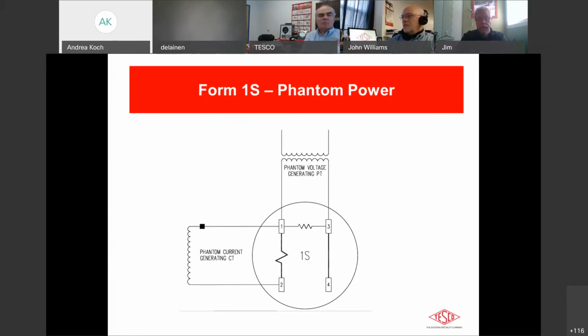so that's a big use for a 1S installation these days. Right, and actually, I did a TESCO Tuesday presentation a few weeks back on smart metering, which is these smaller format meters that are going onto LED streetlight poles and measuring some other interesting applications where you need a small format meter. Their meter form is basically a 1S, right? They've got a single coil for the voltage and a single coil for the current. There's some other electronics in those devices used to control the output, so they're dimming lights and turning them on and off and things like that. But in essence, the metrology for those devices follows a 1S meter form.